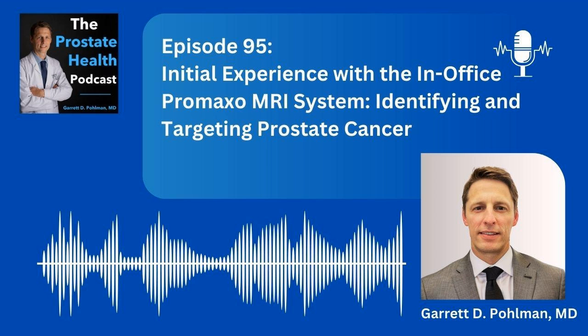You certainly have some flexibility in terms of where you want to use the system. Not only can it be utilized in the hospital and surgery center, but it can also be employed in an office setting. At Carney Urology Center, we decided to set up the system in our clinic. With its small footprint and the fact that it does not require significant facility upgrades to install it, it was an easy install. The minimum room requirement is a 10 by 10 foot room — our system easily fits in a 10 by 12 foot room in the clinic. We just added a 220-volt plug in the room and we were ready to go. The most common procedure table being used for the Promaxo biopsies is the Avant Torino 550 table, which is the one we ended up going with. It is easy to move around and the piston-type stirrups for lithotomy attach easily to the side rails of the table. From a workflow standpoint, it has been pretty seamless in the clinic setting. I'm able to see other patients while they are performing the MRI scan and registration process, then pop back in to take the biopsies, which takes about 8 to 10 minutes.